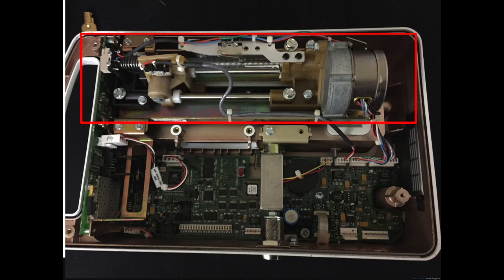And then comes the biggest, the most dangerous piece of the entire pump. That is this linear actuator, which pushes a plunger up and down on the actual drug to push drugs through an IV, right? So if you're looking to do what the government calls effects on a device, to make it dispense drugs at a rate that it's not supposed to, ultimately what you have to do is basically turn this thing on. Right?